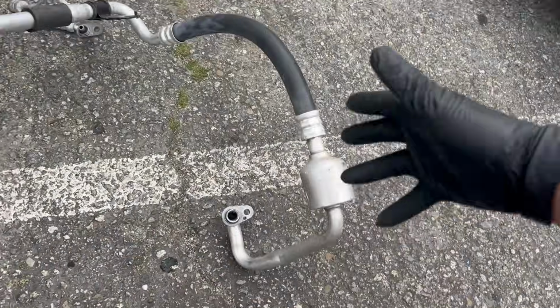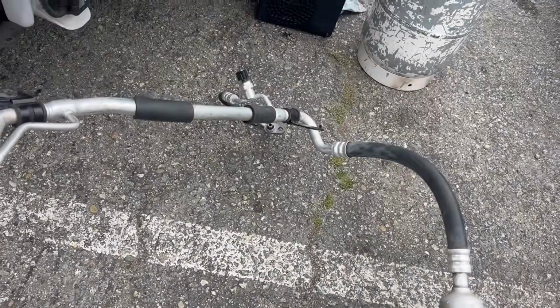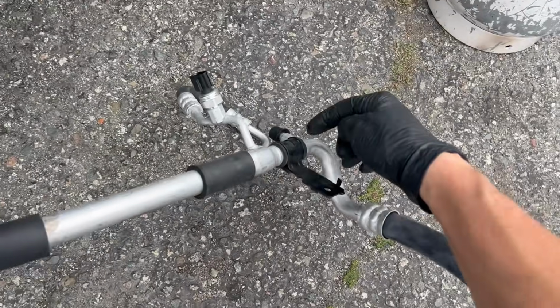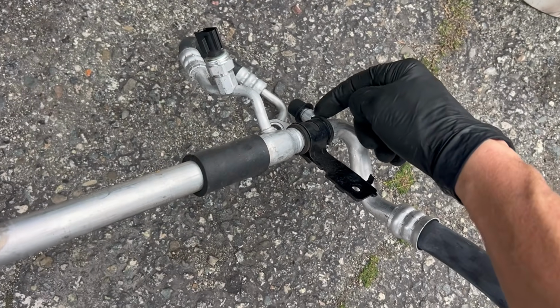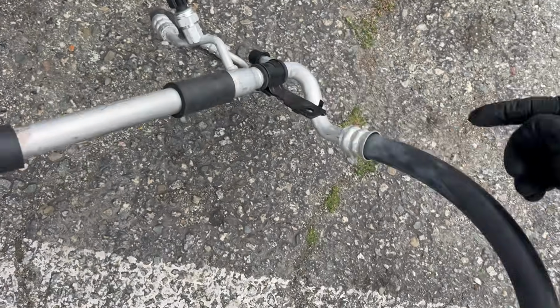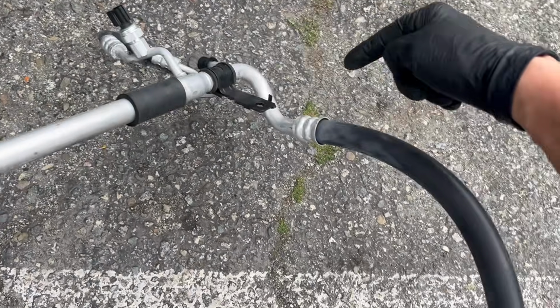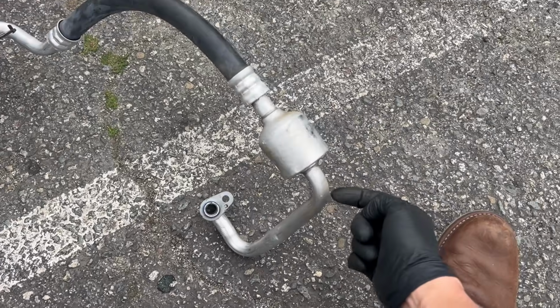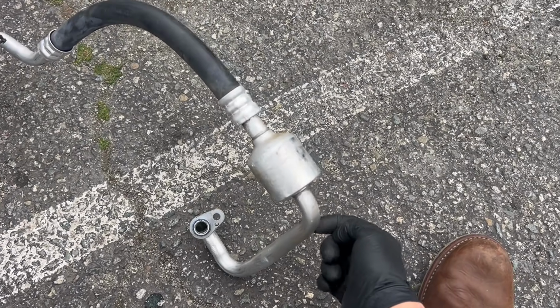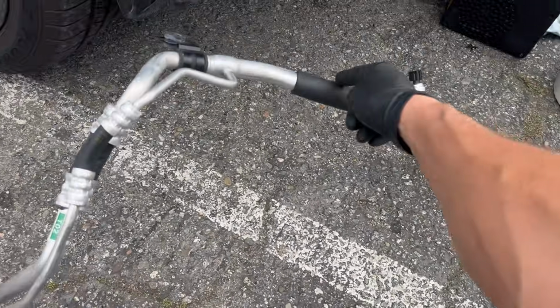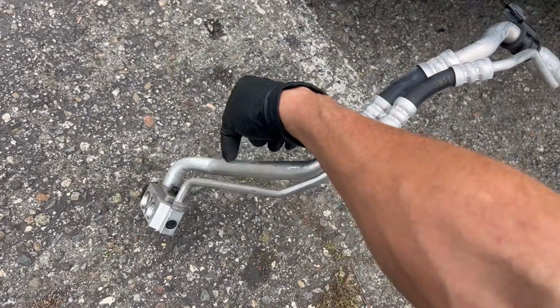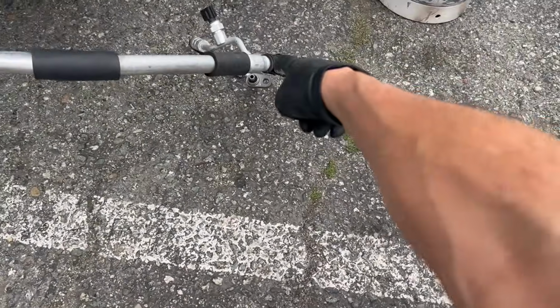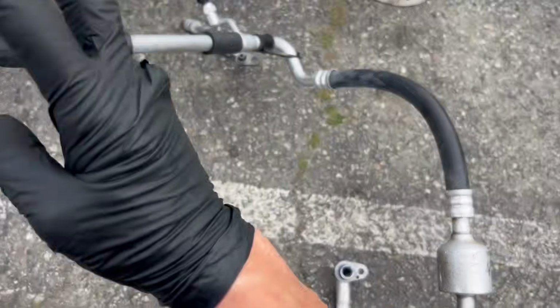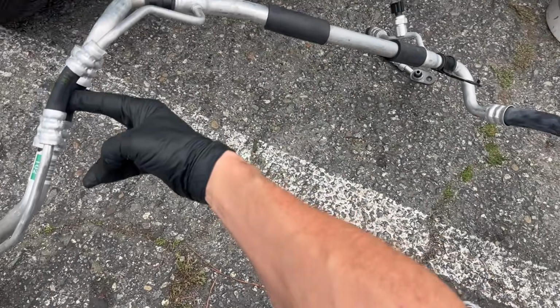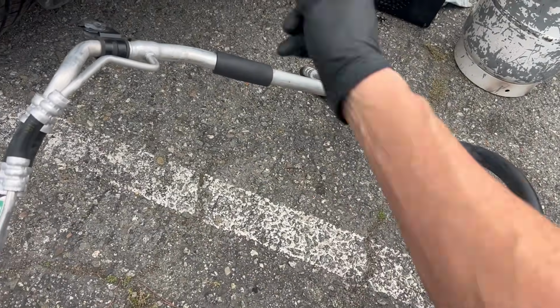There's not always a temperature drop under that condition. So this is all stuff you can do in your class. You can make restrictions, and you can purchase the taps for your fittings here. You can purchase these fittings for a few dollars a piece, and you can do things like, here's the factory one. Well, see this rubber hose? You can drill a hole right here, and you can put another tap here for a pressure sensor so you can have your gauges hooked up. Then you can come over here and you could put another one right here before the expansion valve. So you have a low side fitting, that factory low side fitting, and another low side fitting. And on the table, up on the wall, as an instructor, you could put clamps across the hoses and see the temperature drops and the pressure drops.